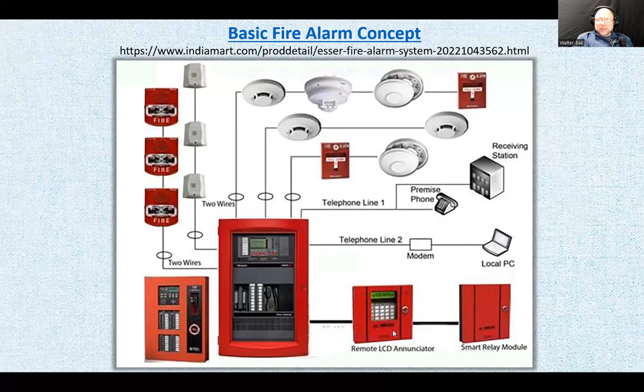All right, now how does the zone work in the fire alarm as opposed to the security alarm? Now remember, with security alarm, do we have that? No, we don't. With the security alarm, it was just a zone, so it would be a common point here, and there would be the sensing input. So there you would have one series closed loop, and if the loop opens, then that means it's alarm. Now with the fire alarm, it's a little bit different.